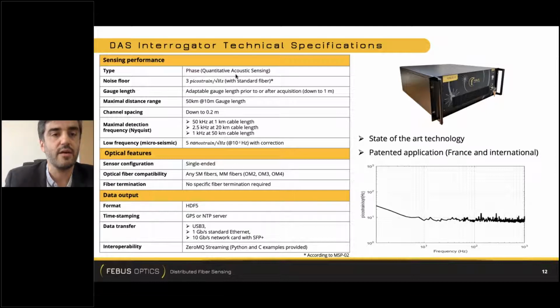we can give a noise floor figure of 3 picostrain per root square of hertz. This is obtained with standard fibers. As I said before, and I will show you why it is important, we have the capability of changing the gauge lengths prior or after acquisition, meaning you have your data and then you can reprocess your data several ways to obtain several results with several gauge lengths. This is a unique feature from FEBUS Optics.